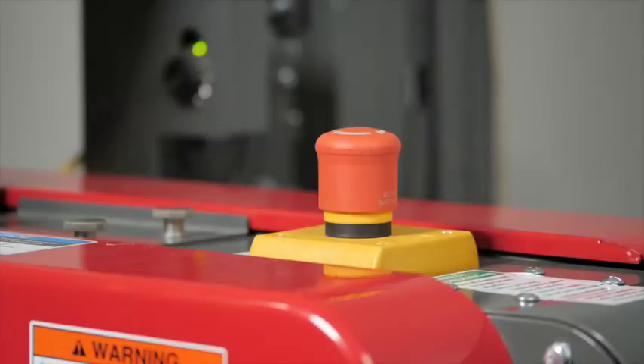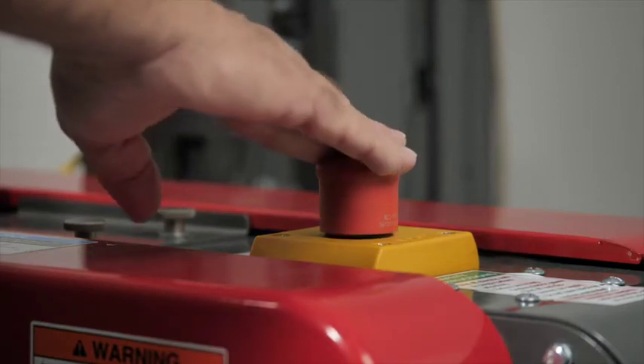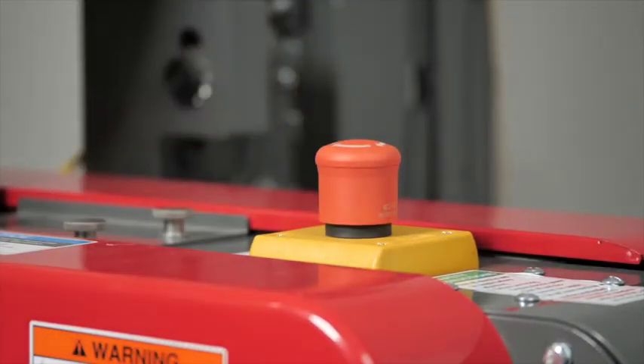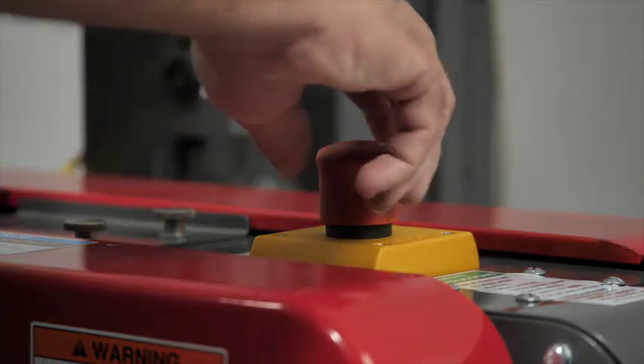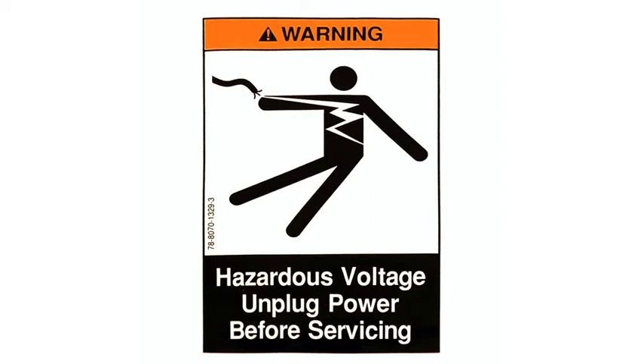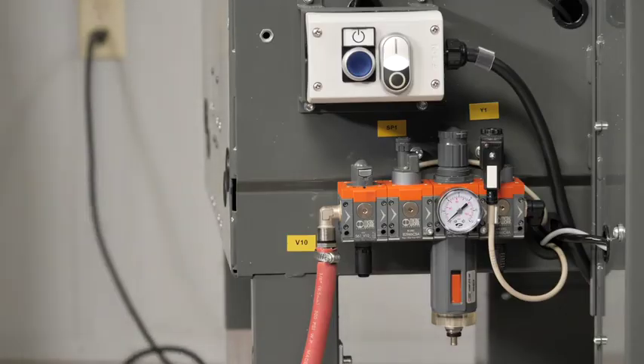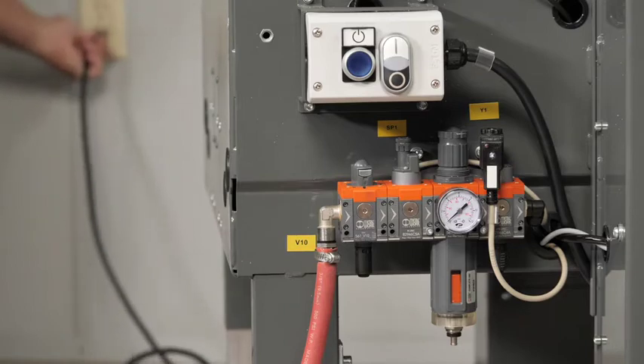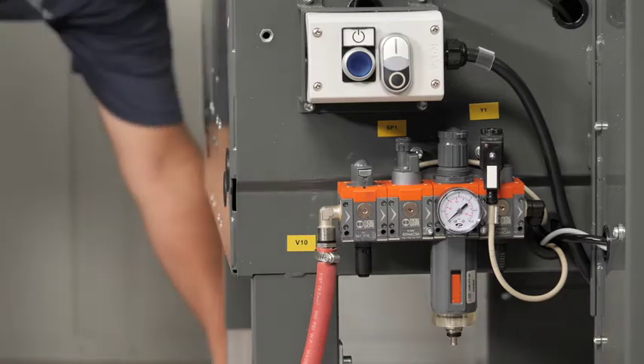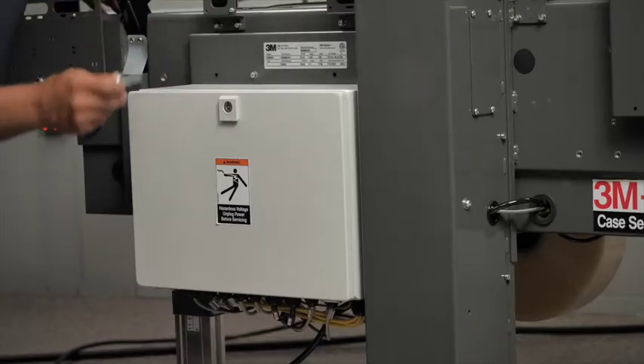The emergency stop push button is located on top of the upper assembly. Depress to emergency stop the machine. Twist to unlock the e-stop before resetting the machine. The electrical enclosure contains hazardous voltages, so be sure to unplug the power cord before servicing. Refer to the instructions and parts list owner's manual for the electrical schematic diagrams.